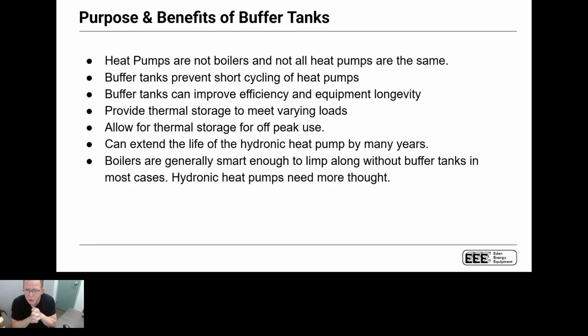The other thing that's really important is we want to make sure we don't short cycle the heat pump. Typically what comes into play is people will say, well, I have an inverter, it's going to modulate, I don't need a buffer tank. I have firsthand experience on how that can be a big problem for you. We're going to talk a little bit about that.